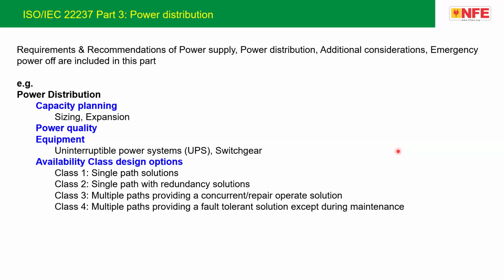We are going to connect with cables, because in one data hall the capacity can go up to 4 megawatts. In that case, with the transformer sizing and the cable sizing, the heat within the room and within the panel will be huge. So we have to take care of that, compile the type test report, and select the switchgear accordingly.